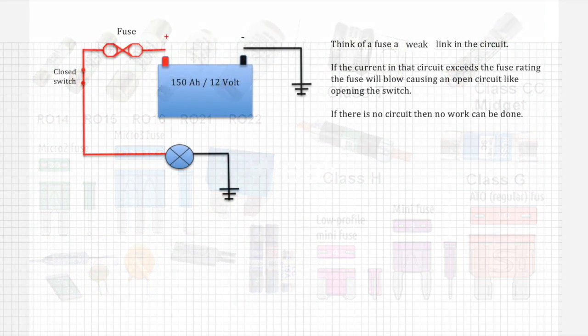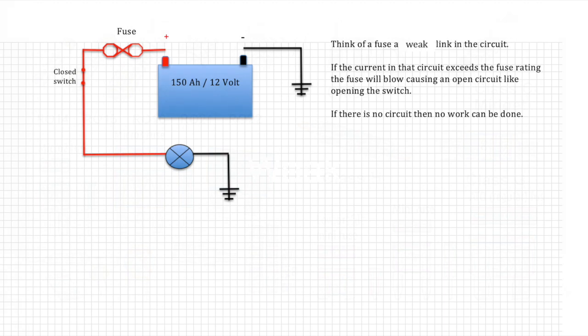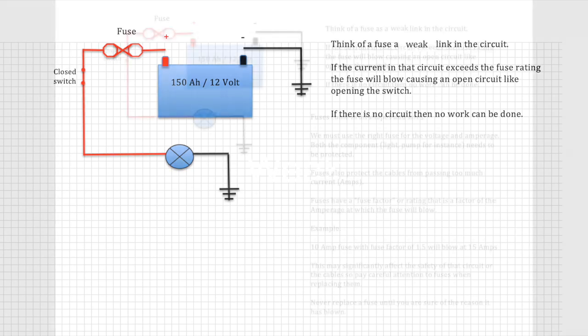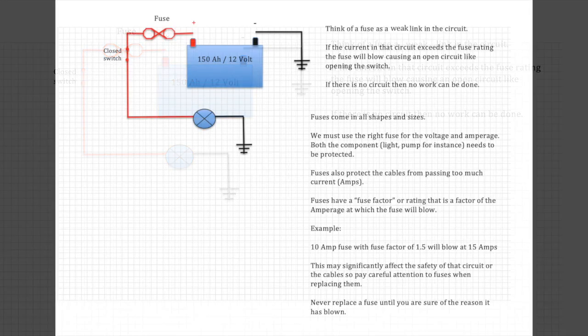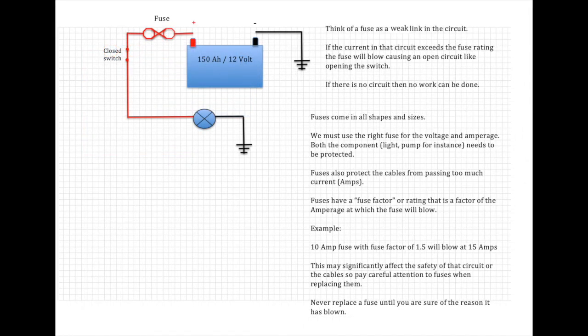So I said to think of a fuse as a weak link in a circuit. If the current in that circuit exceeds the fuse rating, the fuse will blow, causing an open circuit, like opening the switch in a way. If there is no circuit, then no work can be done. So we need to make sure we have the right fuse for the voltage and amperage. Both the component, the pump or light for instance, and the cable needs to be protected. Fuse also protects cables from passing too much current, in the same way.